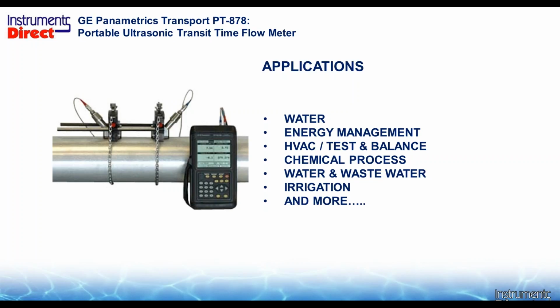I got sludge, oatmeal. I've got a quarry application. I've got a mining application. I've got 10, 20, 30% solids. That's where you put your Doppler flow meter. Transit time flow meters traditionally work on ultra-pure liquids up to about 2% suspended solids, and that's a fuzzy number depending on the kinds of solids. So you heard me: if you've got everything other than sludge, then a transit time flow meter is probably the way to go, which is the bulk of your applications.